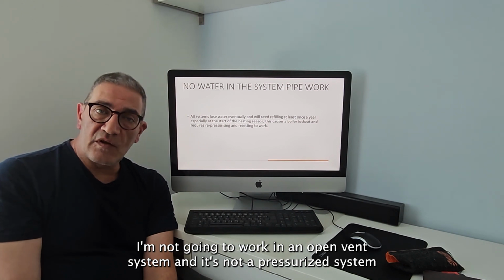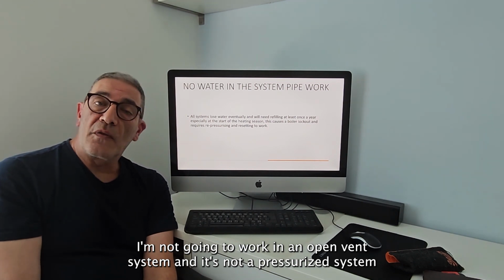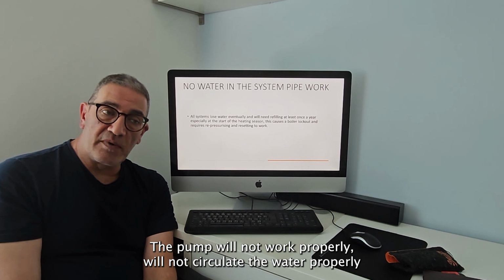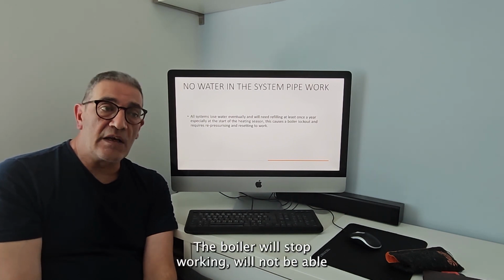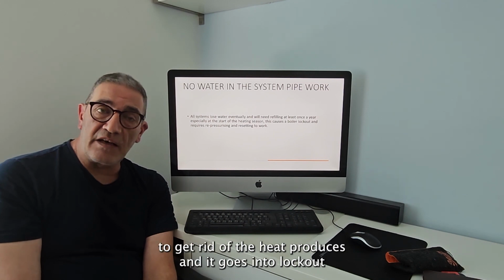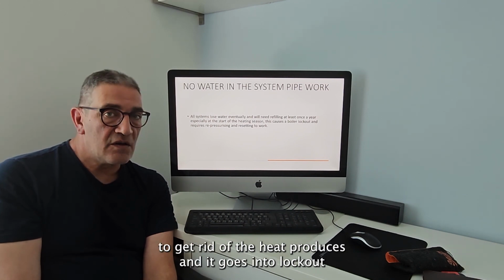In an open vent system, which is not a pressurized system, the pump will not work properly and will not circulate the water properly. The boiler will stop working, will not be able to get rid of the heat it produces, and it goes into lockout.